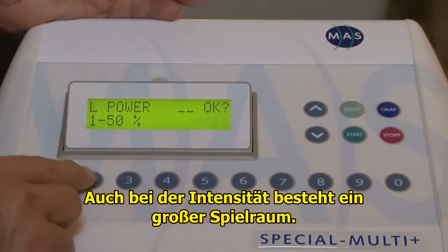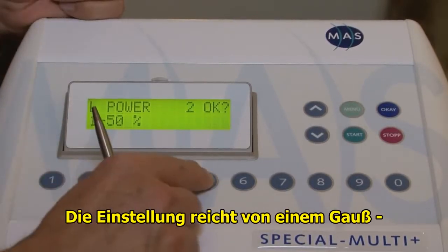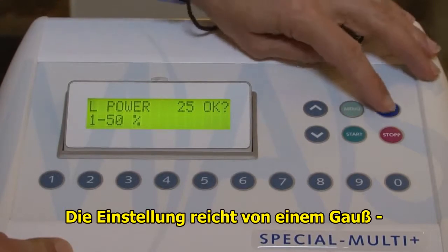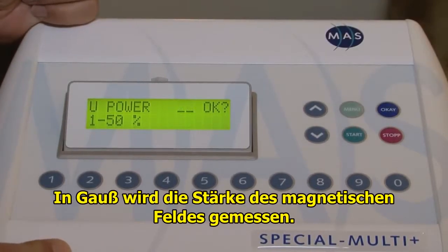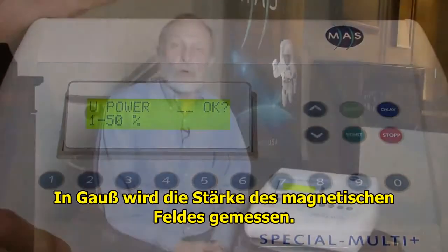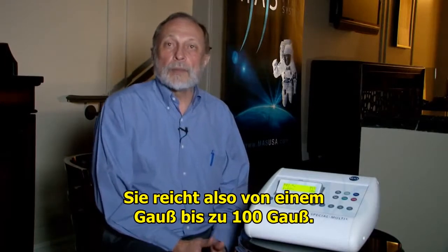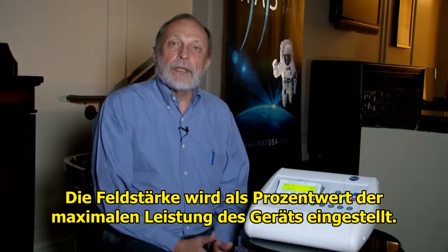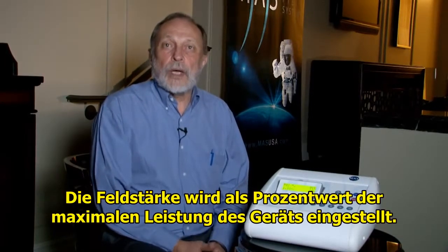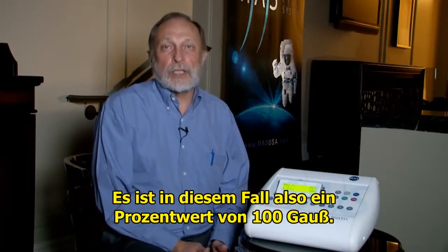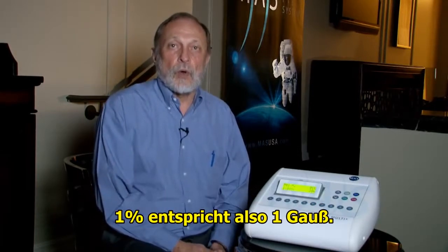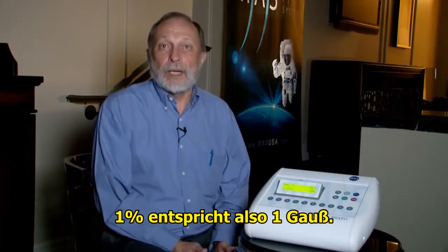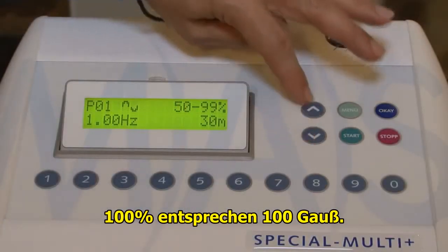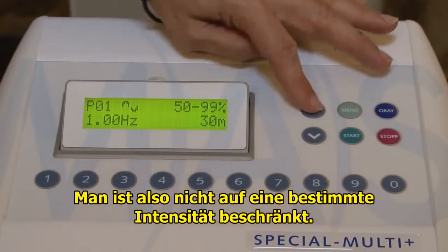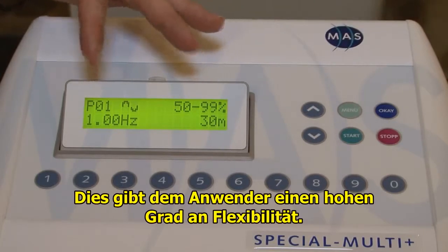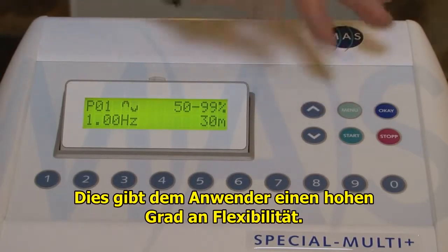There's quite a bit of latitude as well with intensity. You can go anywhere from about 1 Gauss, and Gauss is a measure of intensity of magnetic field. So it goes anywhere from 1 Gauss all the way up to 100 Gauss. The way you make that choice is based on percentages. So essentially it's a percentage of 100 Gauss. So 1% would be 1 Gauss. 100% would be 100 Gauss. So you're not restricted to any particular intensities. So there's a lot of flexibility with what you can do with intensity.